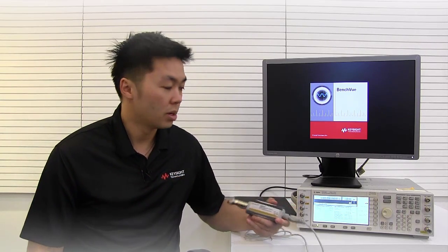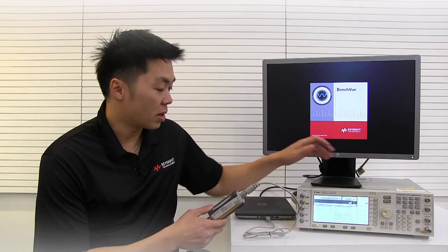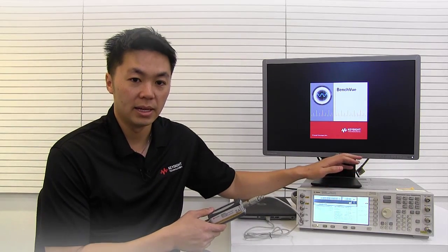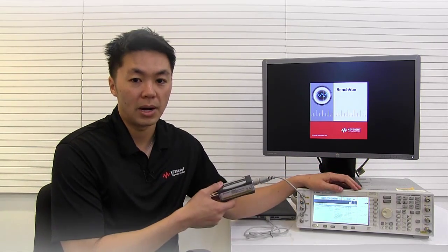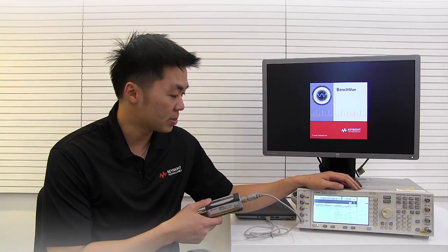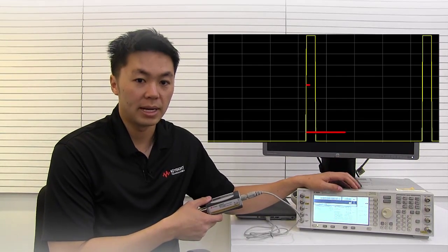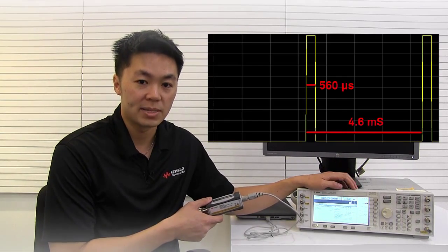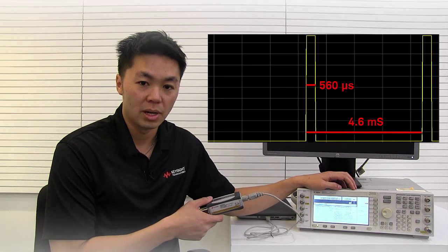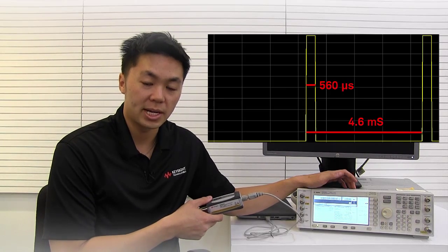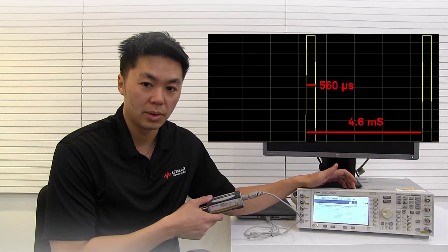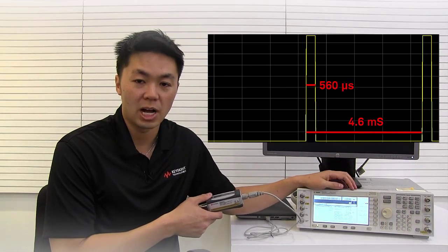So in this video I also have the signal generator that I can use to provide a signal to my power sensor. Here the signal generator is providing a pulse signal that has a 4.6 millisecond period with a 560 microsecond pulse width which is actually fairly common for a GSM signal.